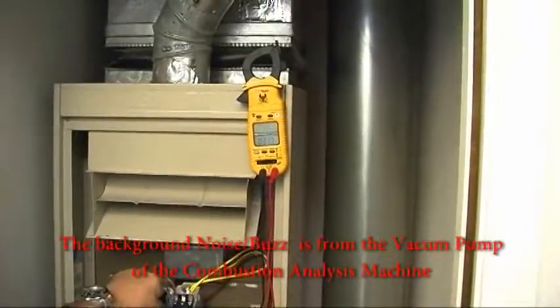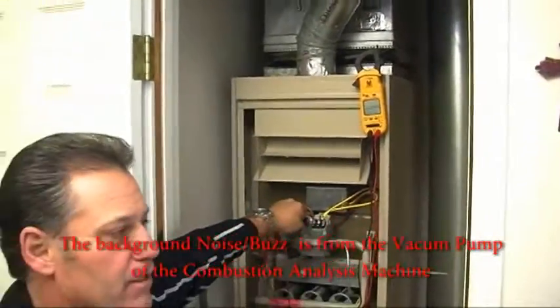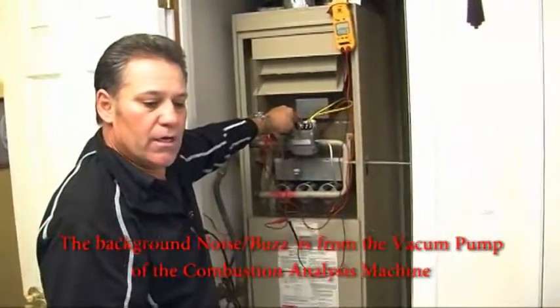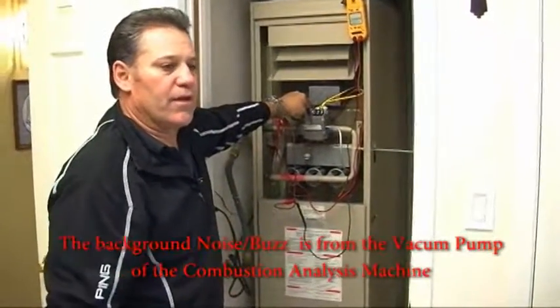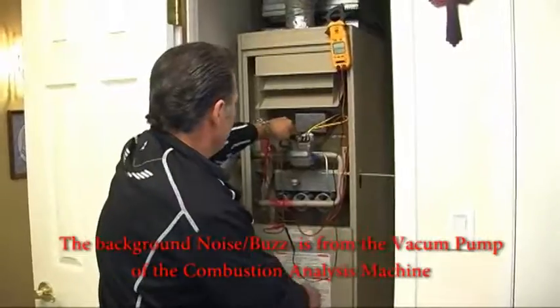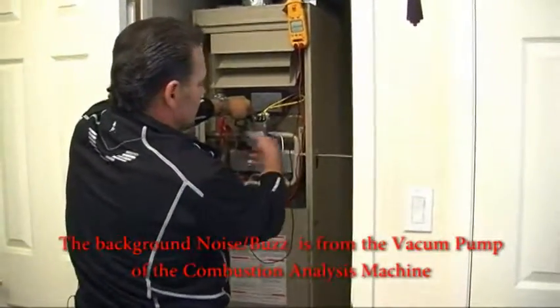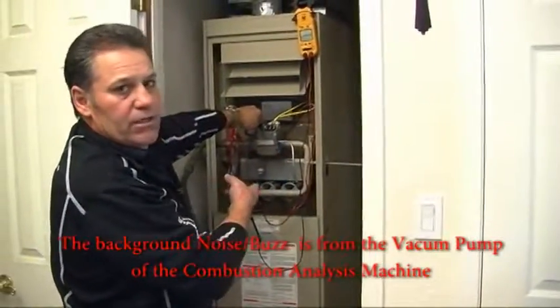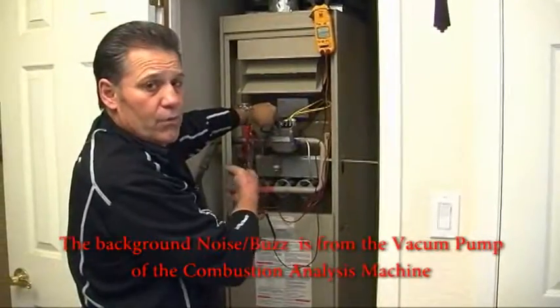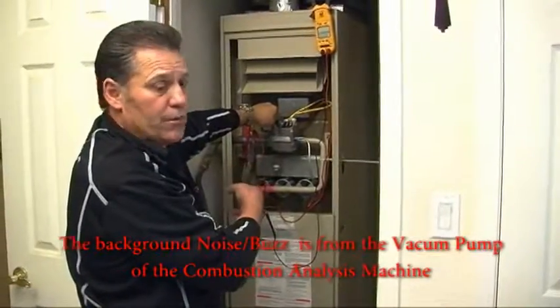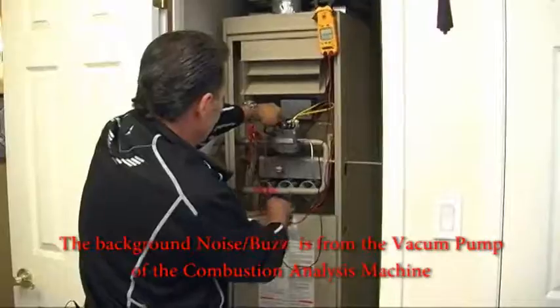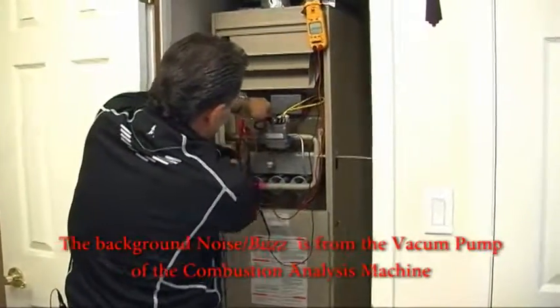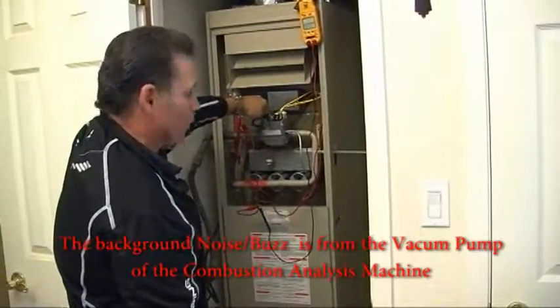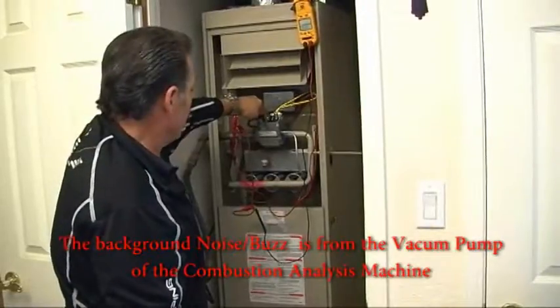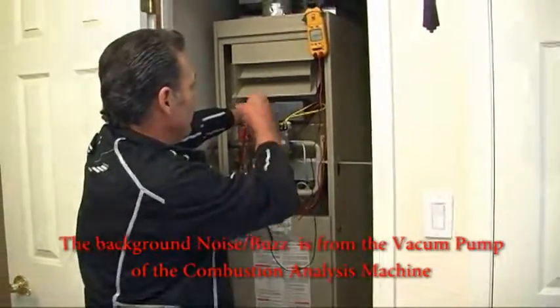Again, just relax while you're watching this, because at the end of this, we're going to pan into some papers where I've drawn up everything and explained all of this to you. I've heard that there's a difference in polarity if you hook up the red, your positive lead, and your common lead, but I've tested both ways. Just make sure that one of the leads goes to the copper sleeve and the other goes to your tin-plated connector, and you will get your reading.